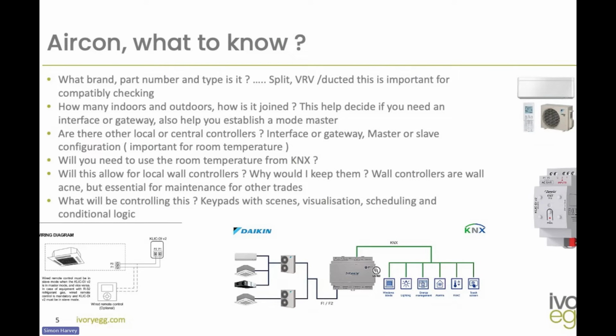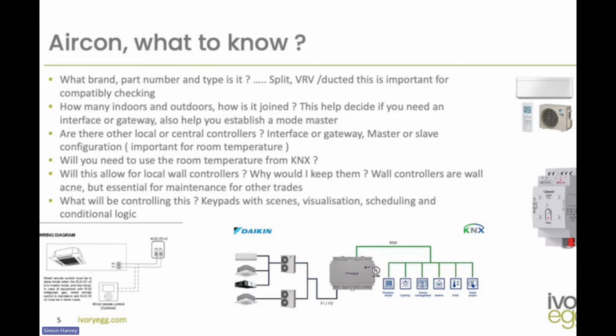There's many manufacturers that make air conditioning interfaces, and they differ from brand to brand, and also from year to year. So a crucial part of deciding what air conditioning interface or gateway you need is working out what the system is beforehand. Check with the air conditioning installer to see how the setup is configured, what type of control it is, and what the part numbers are. Also check how many indoor and outdoor units, and how they're wired and joined. This helps us decide whether we're going to use interfaces or gateways, and it also helps establish a mode master.